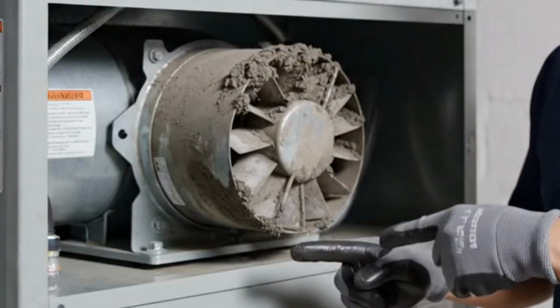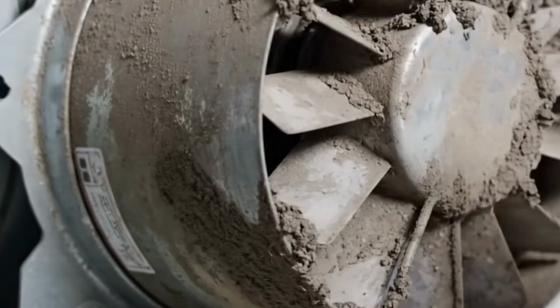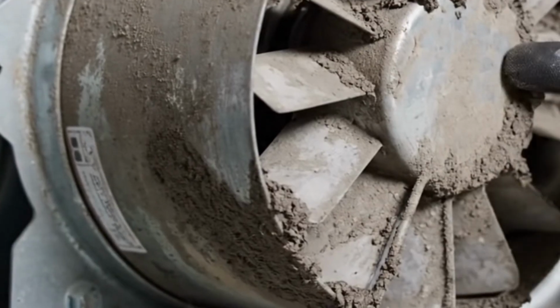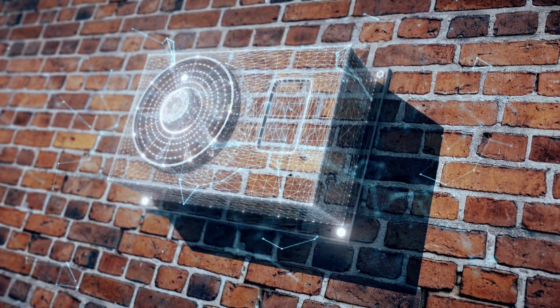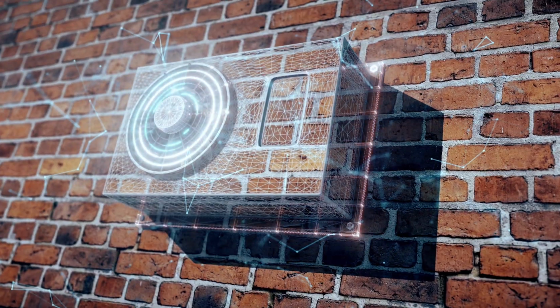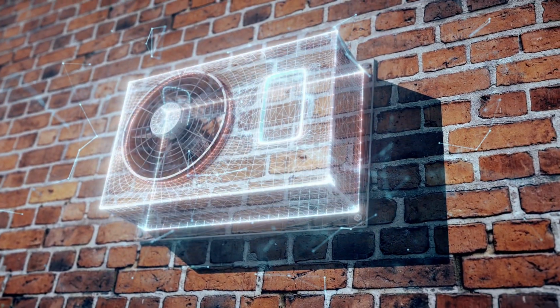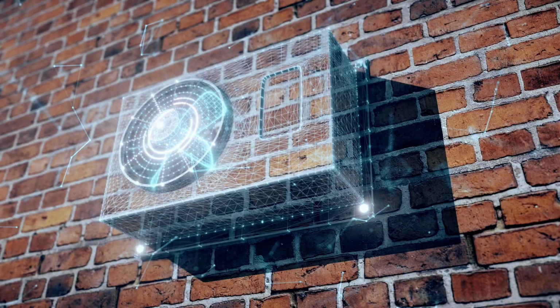So if you hear loud whining or noises coming from the component that moves the air, it's a furnace with a fan in it, air handler, or it's just an air handler for a heat pump. Again, you're looking at a fan motor, a blower motor, as we refer to it in the industry, that again, the squirrel cage, which is what moves the air that is attached to the motor, can get out of balance from buildup of dirt. Very important to have that clean. That getting out of balance will start to make some noises that just don't seem like they belong. Something to get checked out right away.